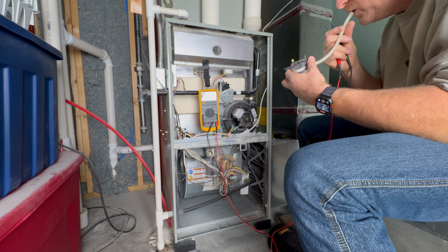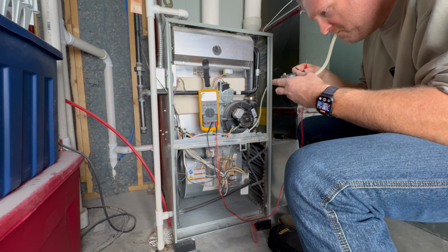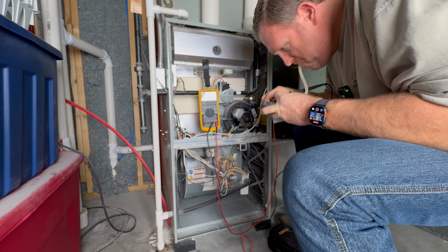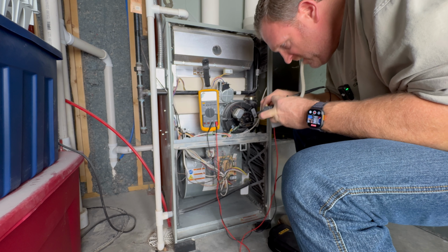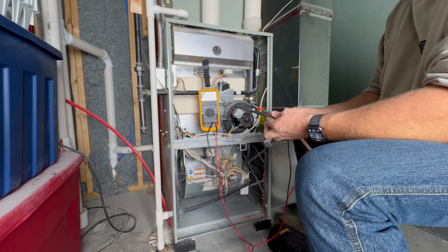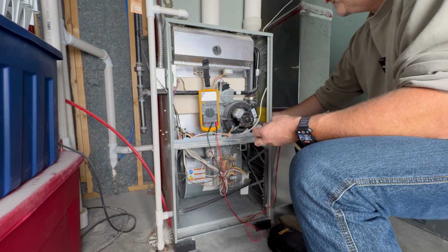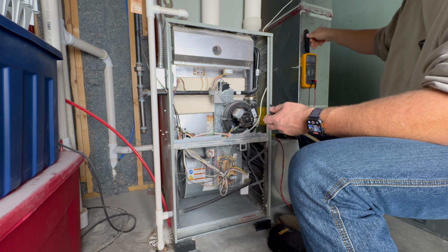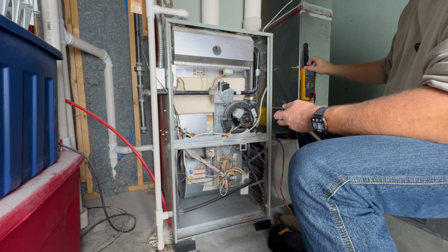Okay, don't laugh, but now I'm going to put some suction on the low side while I hold my meter to the contacts. The contacts close with suction. This switch is good. But what all this tells me is that I have a restriction either on the low or the high side of the exhaust fan. I'm going to check the high side first because it's easier to access and more likely to have a restriction.